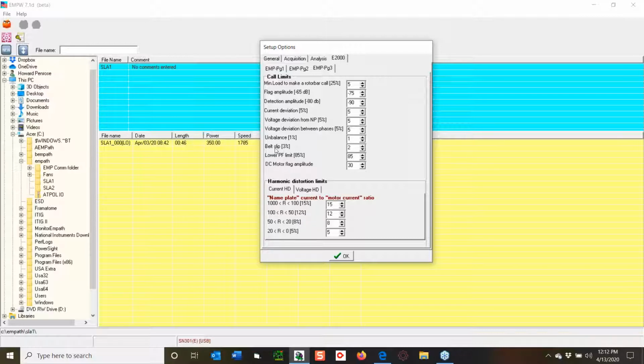So I can put that in there and set all my things. You'll notice down here things like belt slip, so it will make a call on belt slip. The default is 3%, but I like to look at 2%, so it tells me there's a belt slip issue. Then I analyze that set of data closely.